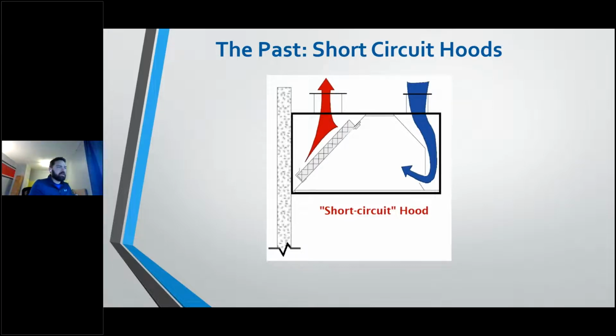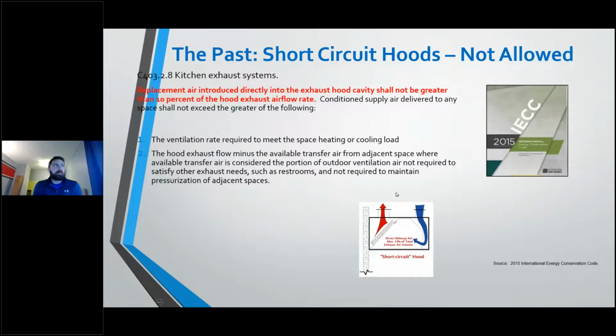But with the advent of CFD modeling and with Schlieren imaging, the industry discovered that with these hoods, the velocity of that supply air moving out of the hood is such that it's impeding the updraft velocity of the exhaust air, and it's actually causing heat rollout, and it's putting pressure on the HVAC system as a whole. So IECC 2015 came out with this statement: replacement air introduced directly into the exhaust hood cavity shall not be greater than 10% of the hood exhaust airflow rate. Now, if you remember, that direct makeup air was 90% for balance. Well, now it can't be over 10%. So that essentially eliminates the short circuit hoods.